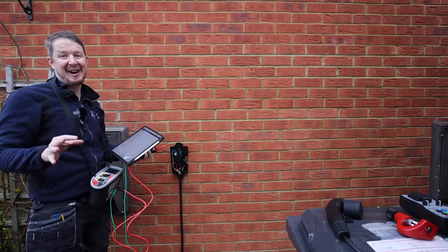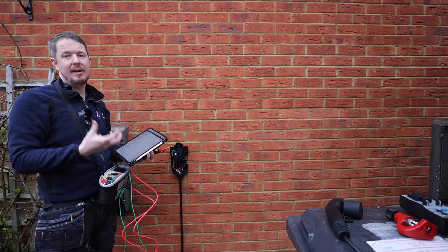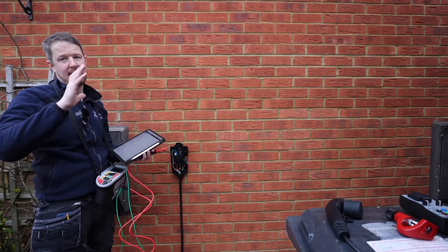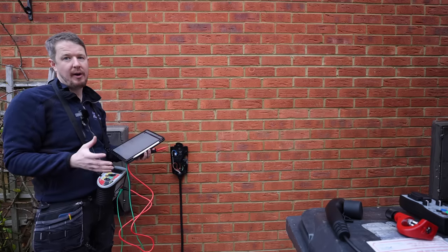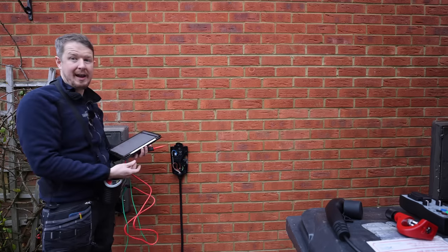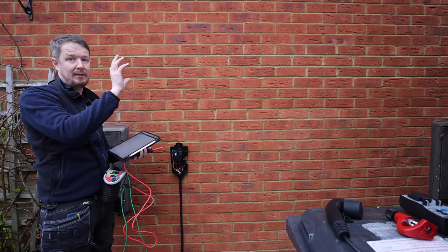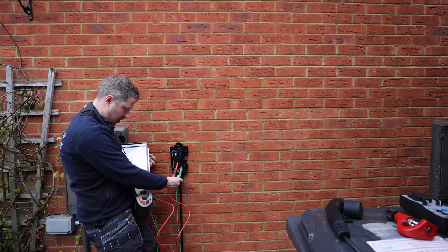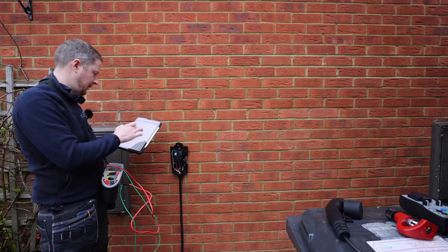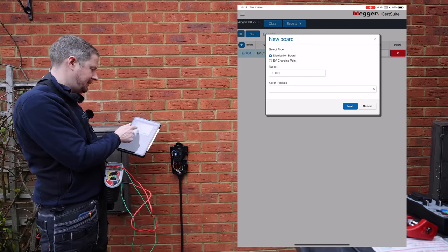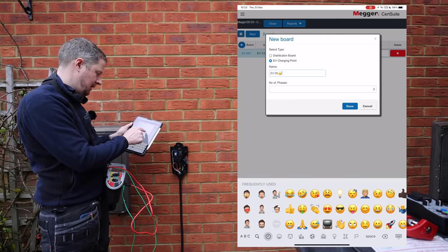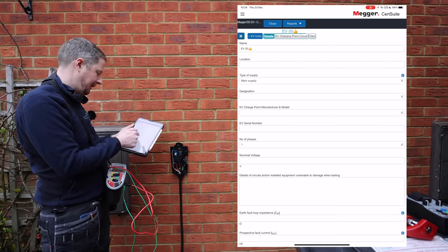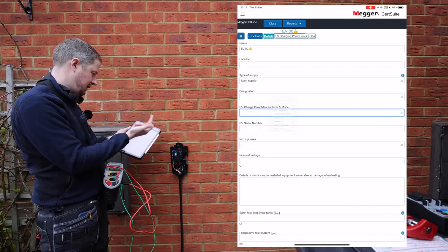I promised I'd show you guys how I do the certification for the EV chargers. One of the great things about Cert Suite is that they have their own EV charger-only certificate format that you can use, which makes a beautiful document that you can send to your customers with all the details of their EV charger, including the test results. So I'll show you what the final PDF looks like, but now I'll show you the test procedure that we do and how we put the readings in. I've got the charger cover off here, I've got my R1 and R2 link, so that R1 and R2 are linked out of the board, so I'm going to do the continuity test here. I've got 0.11 for my R1 and R2 reading, so that's great. So in Cert Suite what I do is I'll go to the board section and I click add board, and then instead of selecting a distribution board, I select an EV charging point.